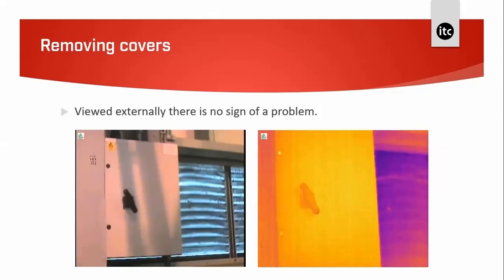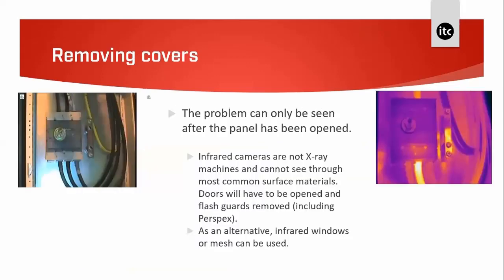What if you're confronted with a room full of panels? Viewing a closed panel, we can't draw much information from the daylight or thermal image — maybe just that the panel door is uniformly a little warmer than the surroundings. The problem can only be seen after the panel has been opened. The doors of electrical panels are opaque solids — it's not possible to truly assess electrical systems without opening them. Even perspex and lexan are thermally opaque to the infrared camera, just like the panel door.